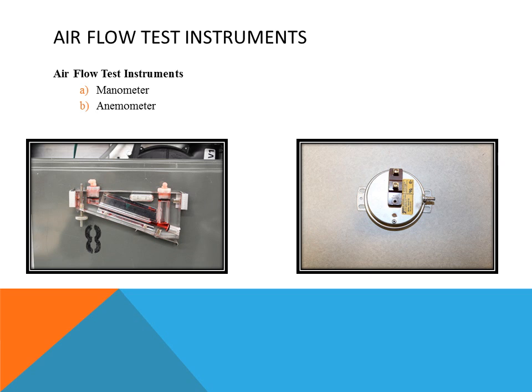For reading airflow, we use what's called an anemometer — a device used to measure the velocity of air. There are many different types of anemometers. A hot-wire anemometer uses a probe with current flowing through it; air movement across the wire changes its resistance, and the meter is calibrated to read airflow based on that resistance — it's a very accurate tool. There is also a vane-type anemometer with a small fan blade that spins based on air velocity. This must be held directly perpendicular (90 degrees) to the airflow; if not, it will throw off the true reading, so accuracy is critical.